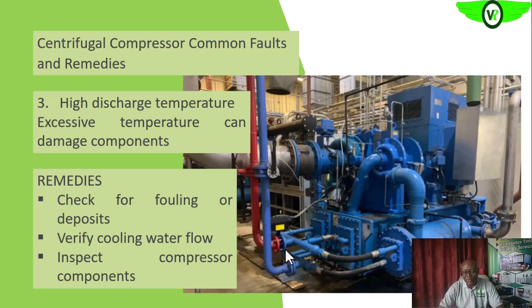So we do not want to forego the normal routine of our inspection, the operational routine too, which is the check of the inlet temperature and discharge temperature. And we know that the inlet temperature will affect the discharge temperature into the compressor. That is the compressor of the gas entering the compressor. This is a two-stage compressor. This is one of the centrifugal compressors, okay, and this is the other.